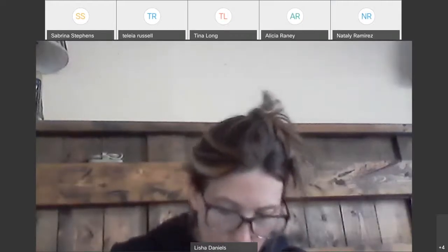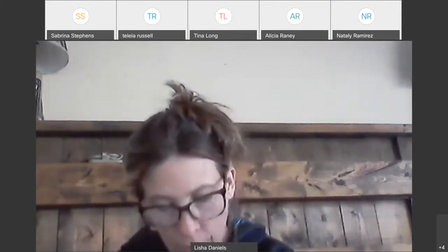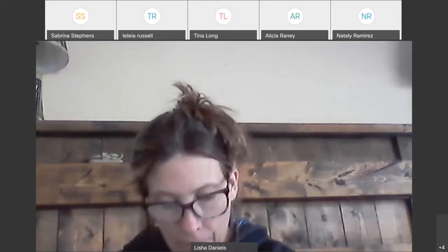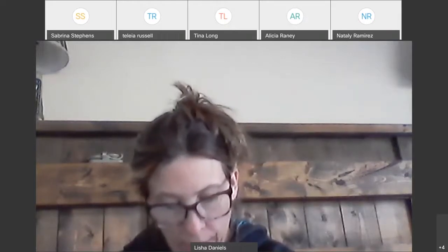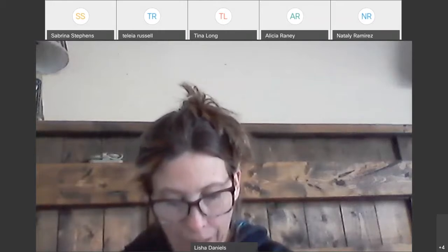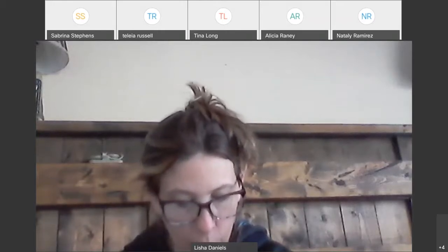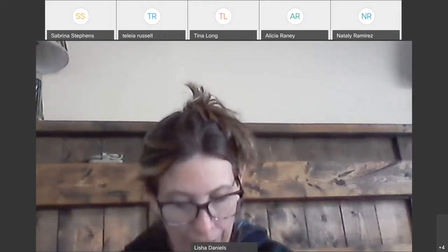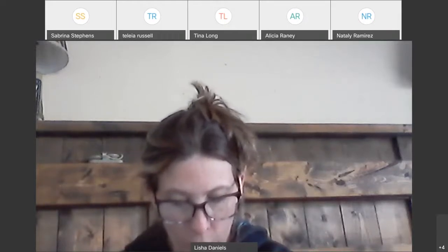All right, control procedure. A control test should be run to ensure that test results are reliable and valid, and that errors that might interfere with test results are detected and eliminated. A control check is performed on an Accu-Chek Advantage using commercially available glucose control solutions. Two levels of control, high and low, figure 19.9, should be used.